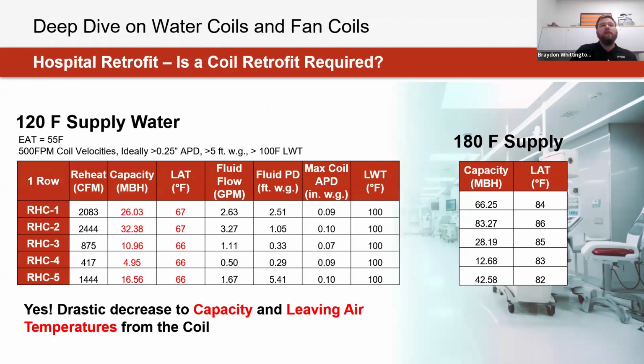And the answer to that being yes. If we were to look at that same schedule and convert and then just instead supply 120-degree entering water temperature to those coils, what we'll see is a drastic drop in terms of not only our leaving air temperature coming from that coil from those similar conditions, but the overall capacity. So you even see this jumping down by 1/3 or 1/2 in some instances now of that same 1-row coil, of how much it's really achieving once we start to pass this different fluid flow that's going through our system.